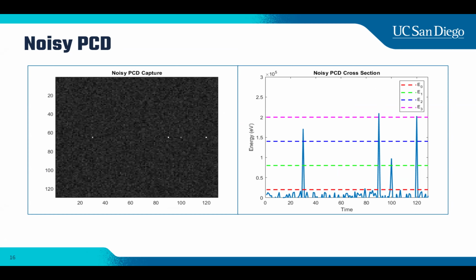20 keV. Okay. Yes. That is what you would set that bottom to, and you say anything below 20 keV, I don't care if it's a photon or noise, I'm just going to ignore it. Yeah, typically, yes. Got it. So that also has the advantage, I guess, that it gets rid of some of the scatter, right? Right. Okay, cool. All right, great.